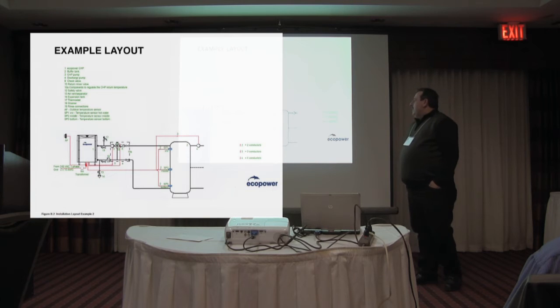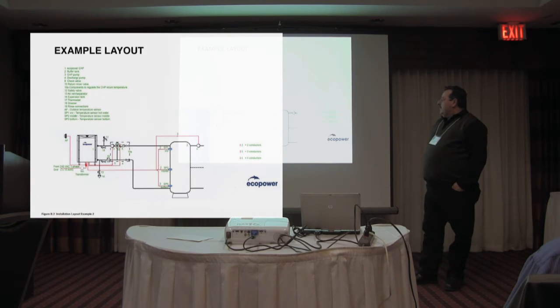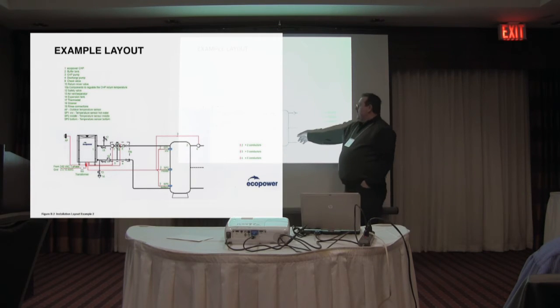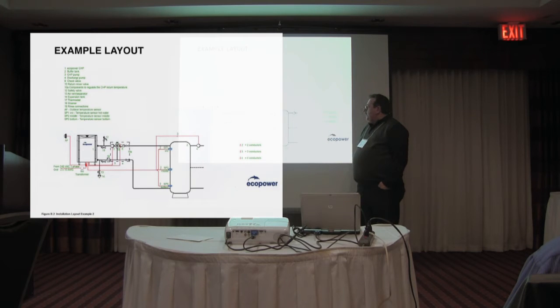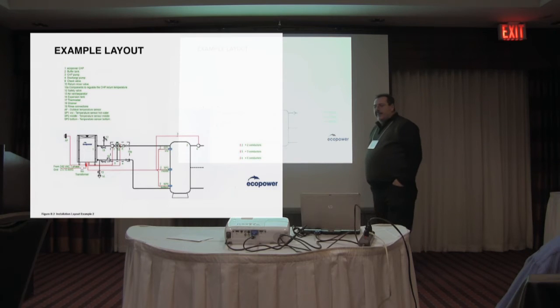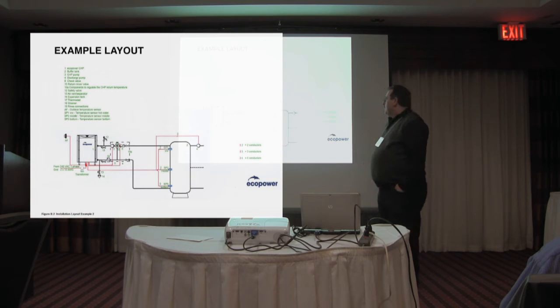So, an example layout, very simple. You've got your CHP, there's a heat exchanger in that CHP, and you can see here that there's a storage tank. In this case, this particular unit, I've installed a few of these units, or sold and commissioned a few of them. It's a 4.7 kilowatt combined heat and power unit, and it's putting out on the thermal side roughly 45,000 BTUs. It'll produce water up to about 167 degrees Fahrenheit. Could actually go a little bit higher, but we try to program in that set point, 167 degrees Fahrenheit.